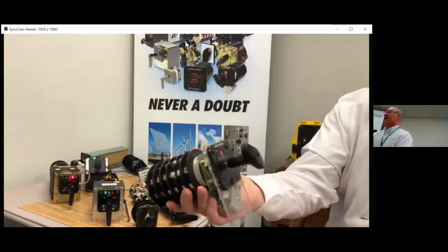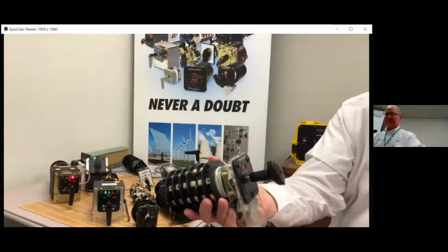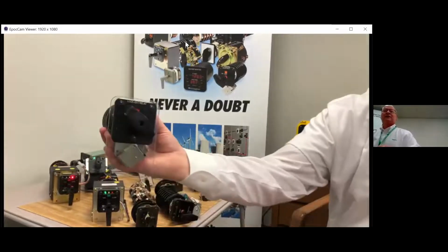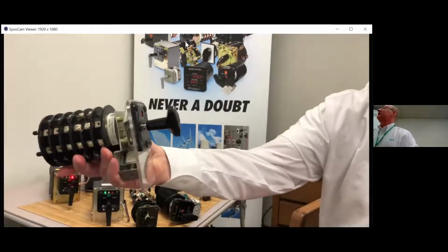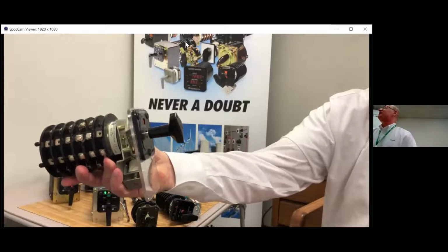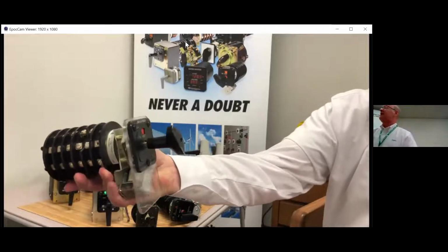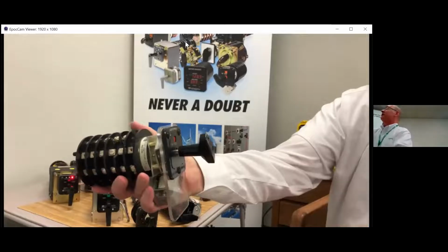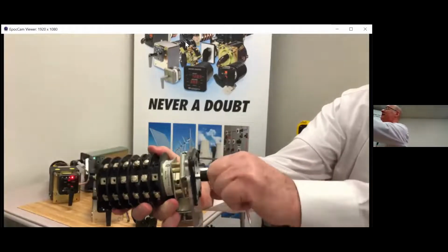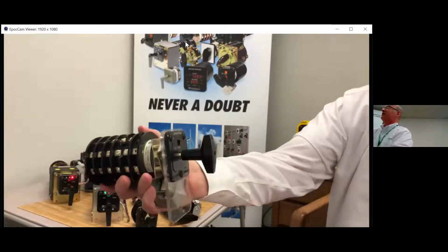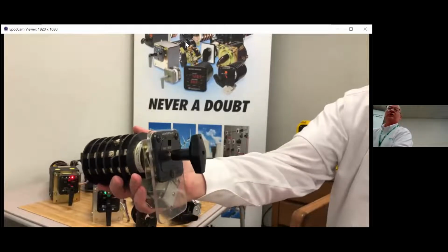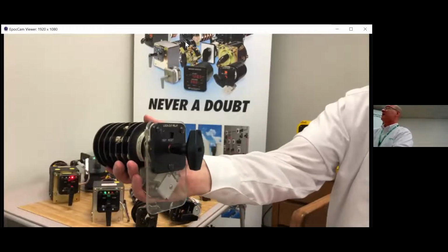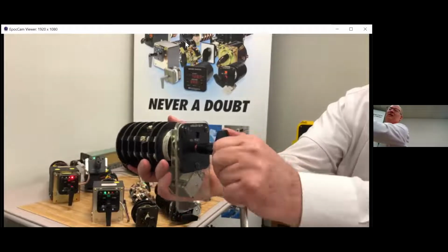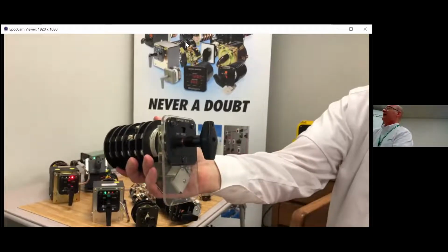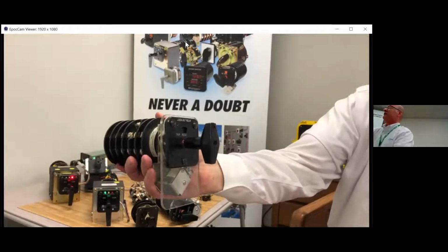I'm going to go to the manual lockout relay first. Now, a manual lockout relay looks kind of like this. It's got a trip and reset handle button on it. But in this particular case, I was in the trip position and I just turned it to the reset position. Now, I cannot manually trip that switch once it's in that position.